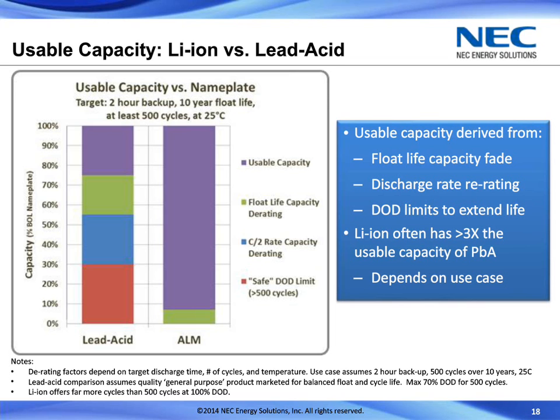And one of those things, the red factor there, is being able to limit the depth of discharge for those cycles. So say in this case, limiting it to 70% depth of discharge in order to get to those 500 cycles over that 10-year period. Lithium-ion, on the other hand, could go to 100% depth of discharge, and the only derating that's really necessary is that little bit for float life after the 10 years, what the capacity loss over a 10-year period would actually be in calendar life.